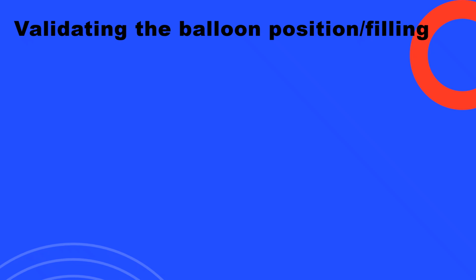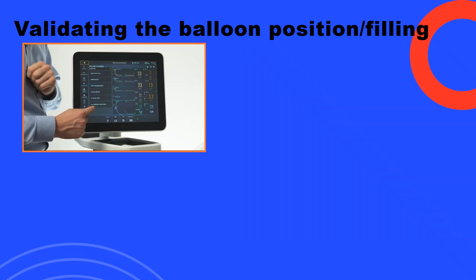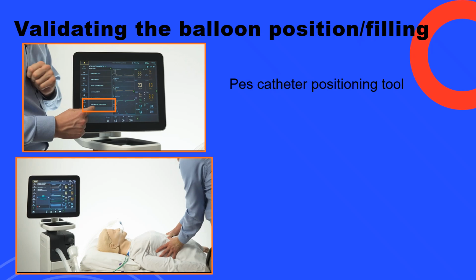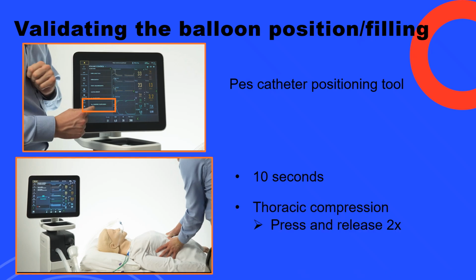The ventilator has a tool that validates the balloon position and filling. Under maneuvers, you have to do a hold maneuver. And this is the esophageal catheter positioning tool. After pressing start, there is an expiratory occlusion that's going to happen. And you have about 10 seconds to perform a thoracic compression on the patient. You have to place both hands on the side of the thorax and press once, then release. Then press again, then release.